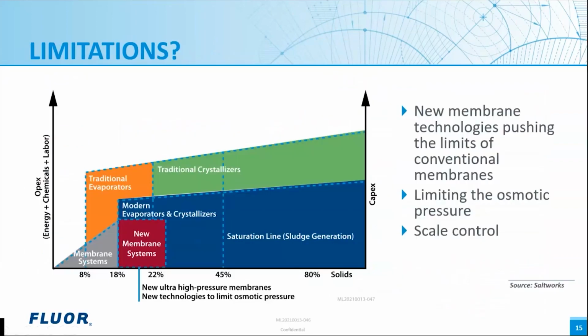Traditionally, several factors limited the overall efficiency of a membrane system. Factors such as pressure, recovery, scaling, and fouling. As will be discussed in the next section, new membrane technologies are pushing the limits of conventional reverse osmosis systems by balancing the overall pressure, preventing scale deposition by various methods, thereby allowing operation at higher recovery.